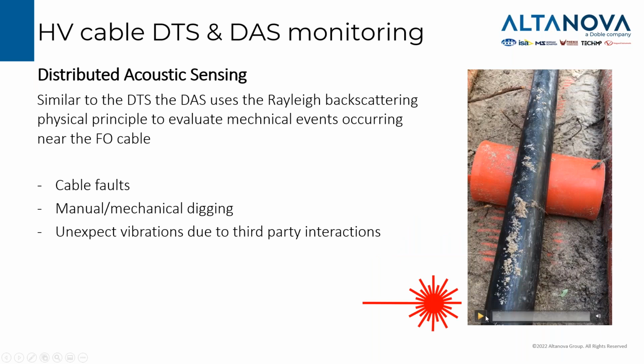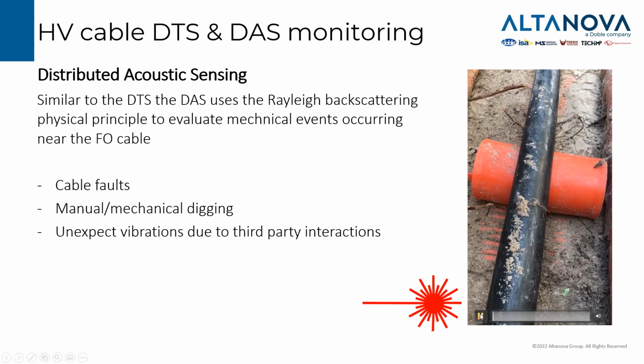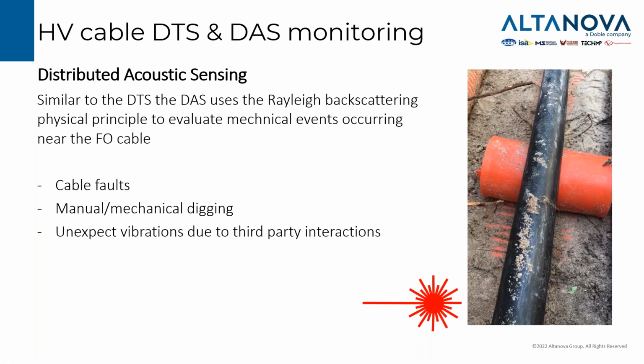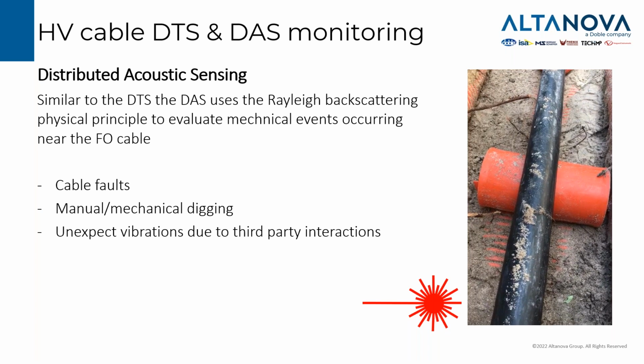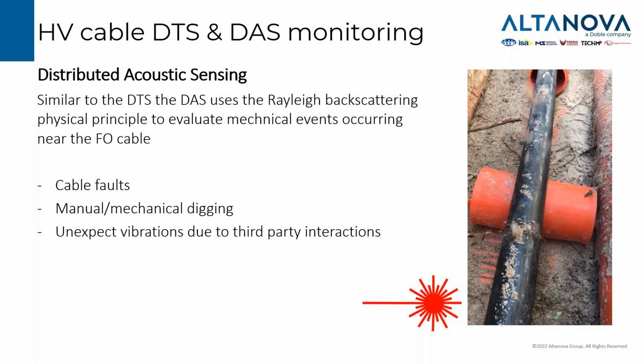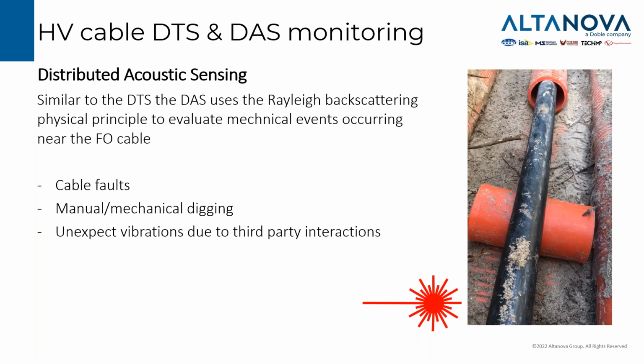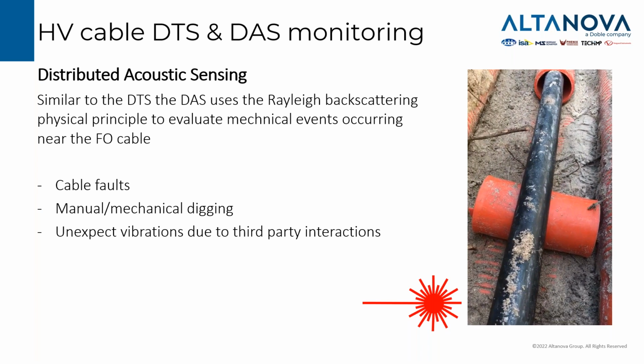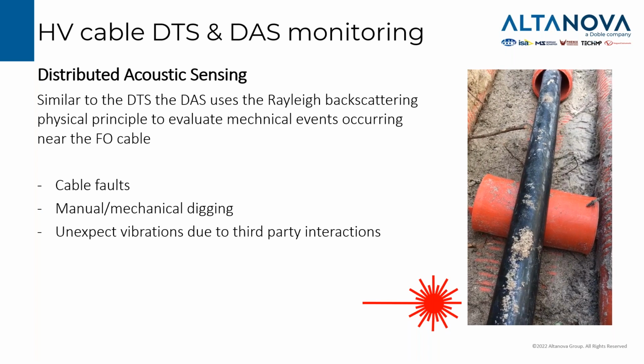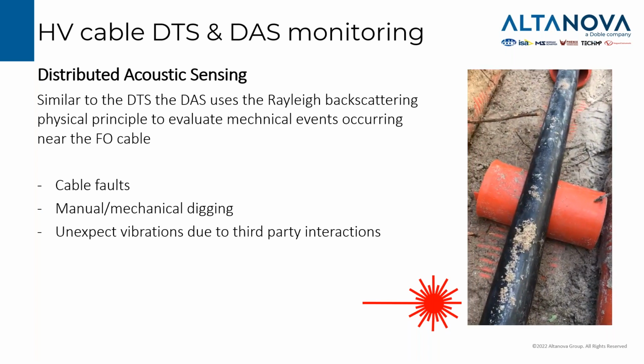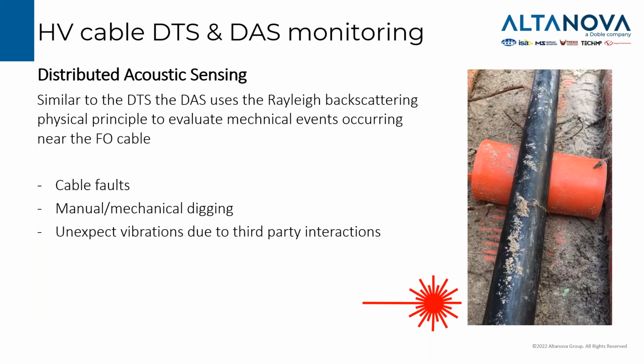Similar to the temperature sensing, the acoustic sensing takes advantage of the Rayleigh backscattering and gives us information about the vibration occurring in the cable. We can see, for example, in this video, PD localization performed on a cable, where we can see how effective it can be to have vibration acoustic monitoring in a cable to hotspot directly the place where we have to dig to find the fault. So we can take advantage of DAS for cable fault localization. It can tell us if there is unwanted manual or mechanical digging nearby the cable. And we can have as well unexpected vibration due to interaction from works, from trains, and so on.